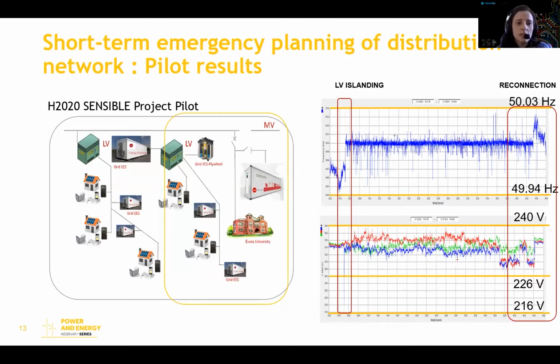So the islanding was also tested in the real field, and we tested both the low voltage island and the entire medium voltage feeder. And as you can see on your right, during the islanding time between these red lines, we were able to maintain a stable frequency and also a stable voltage. There were no big transients. The network was relatively balanced and with a low load. But of course, we are talking about real clients and real consumers, so we needed to maintain quality of service, and this was possible in islanding and with the tools running.